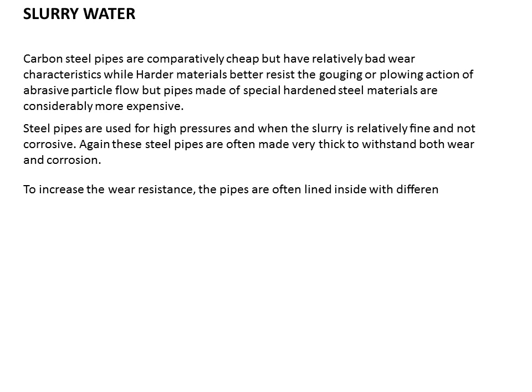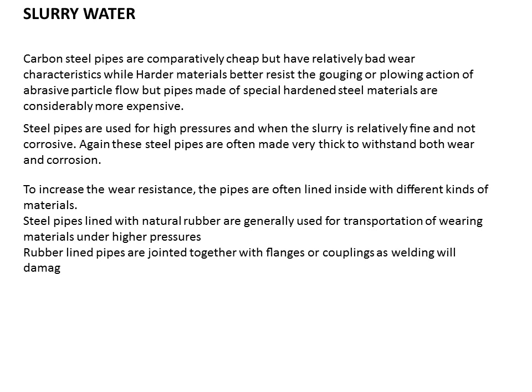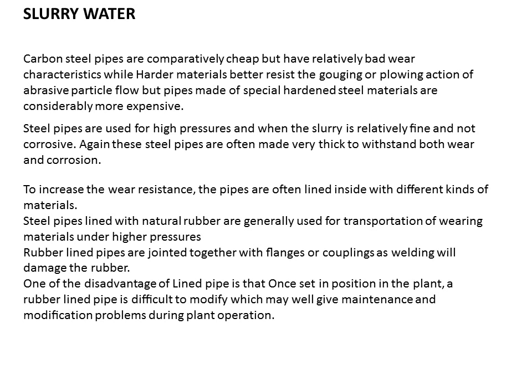To increase wear resistance, pipes are often lined inside with different kinds of materials. Steel pipes lined with natural rubber are generally used for transportation of wearing material under high pressure. Rubber-lined pipes are joined together with flanges or couplings, as welding will damage the rubber. One disadvantage of lined pipe is that once set in position, a rubber-lined pipe is difficult to modify, which may cause maintenance and modification problems. HDPE has proven to be an effective wear-resistant material for slurries.